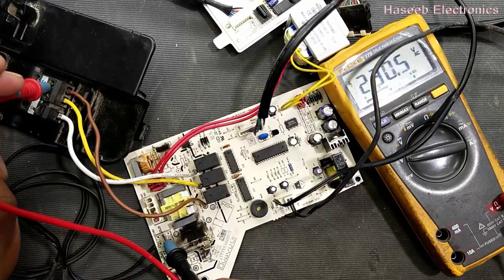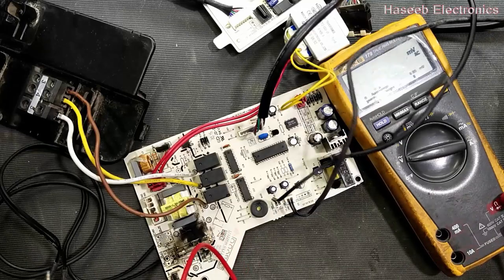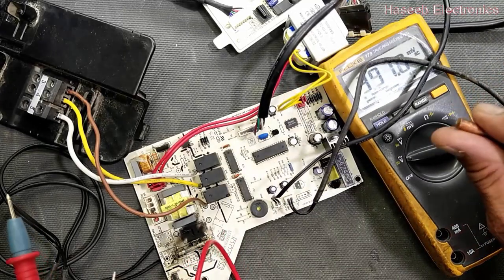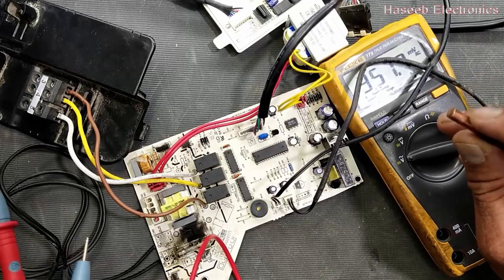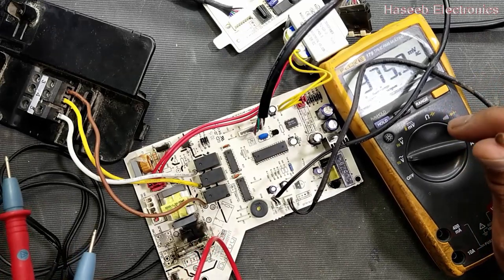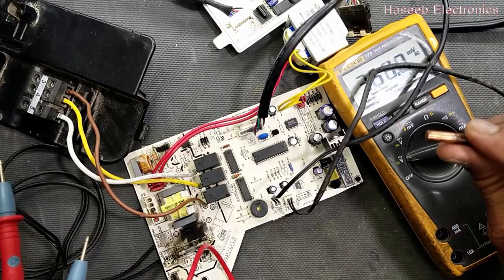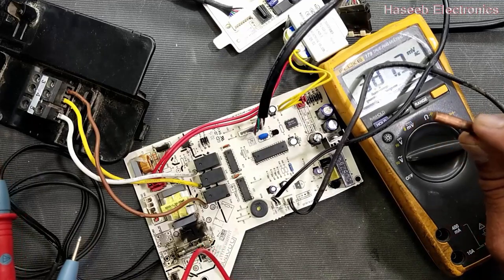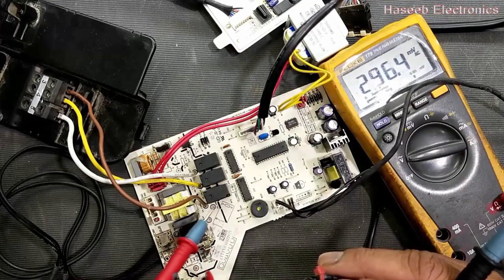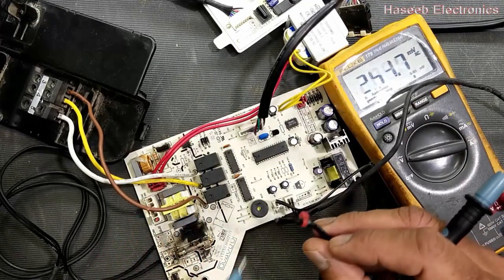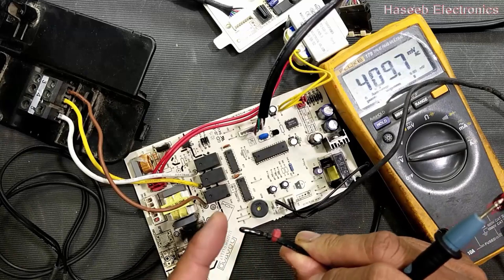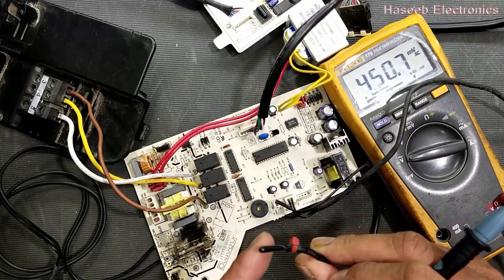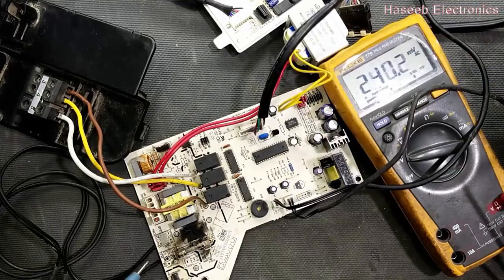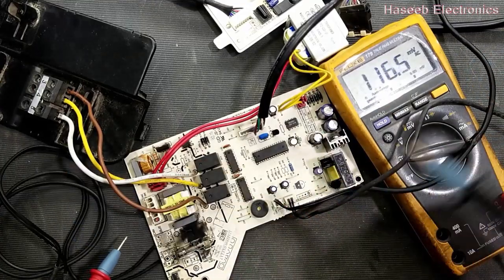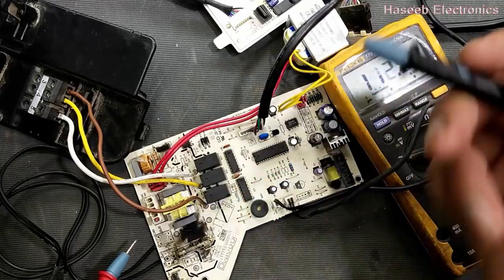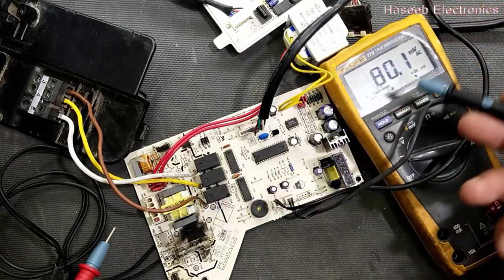So it should wait for a time until it receives a cooling signal from this pipe temperature sensor. If the pipe temperature does not decrease, it will show an error. It will turn the compressor on and off with the change in temperature. When the temperature decreases, it will turn off the compressor. When the temperature increases again, it will turn the compressor on again to cool down.